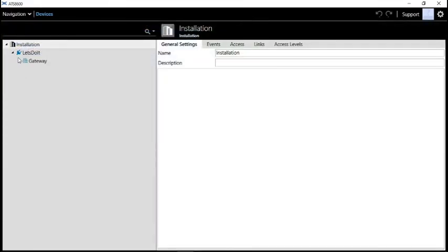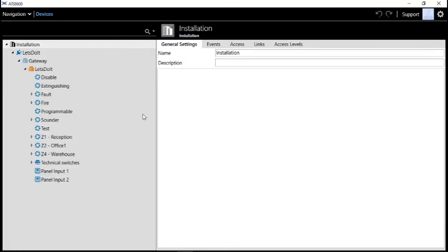And you can see it actually already linked in. This is what you want to see when you start up, that the backend is already doing its work, while the front end, the ATS, the graphical user interface, is linking to the backend. So we're going to do a test with this. I'm going to unclip this smoke detector to make a fault. See if it comes through. And there it displays.